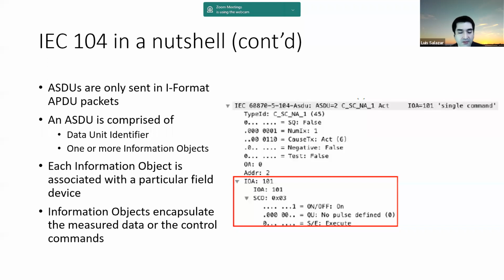So you can have either commands or measurements in this object. Each object has a specific address identifying the specific device that is being controlled by the RTU in this case, and a single RTU may have multiple information objects associated with itself. So you can have one RTU with multiple devices, and each device will have its own information object address, and through a 104 packet, you can issue commands to all of the different devices controlled by a single RTU.